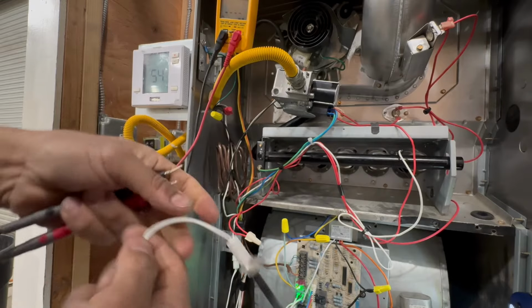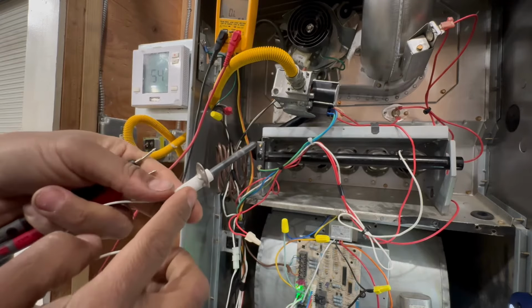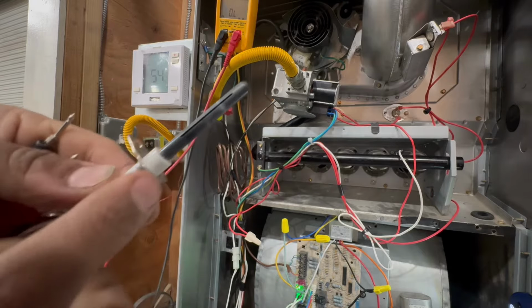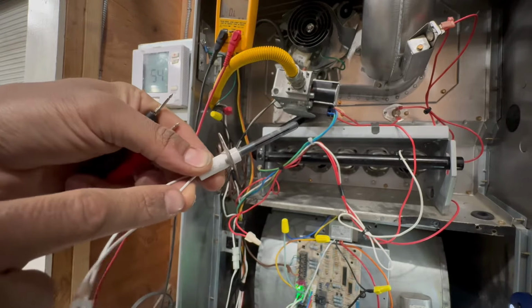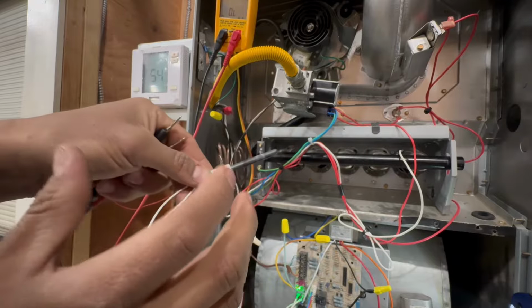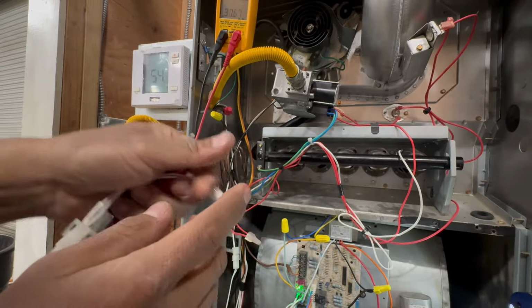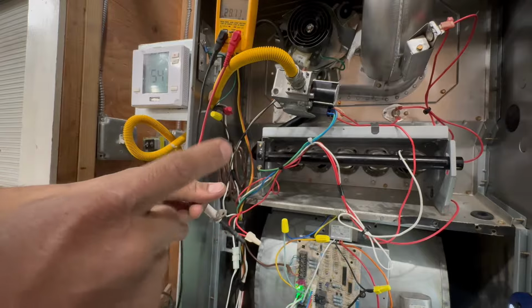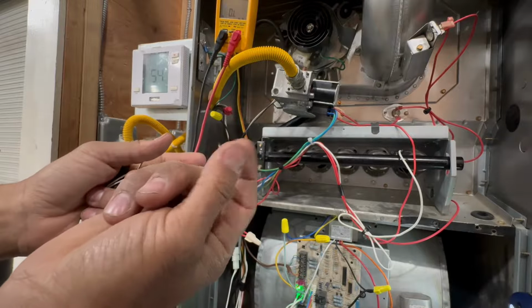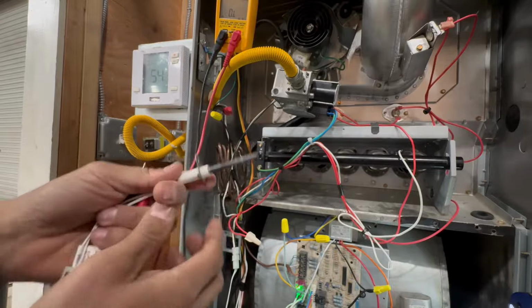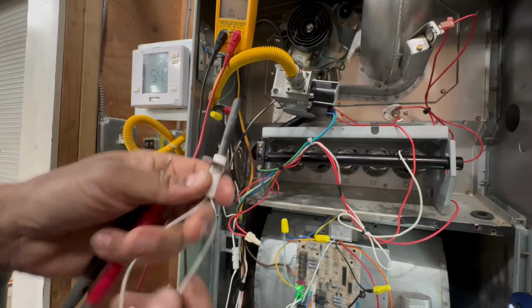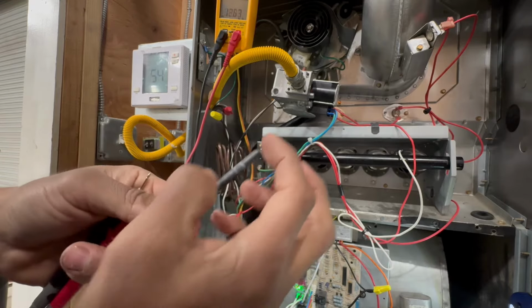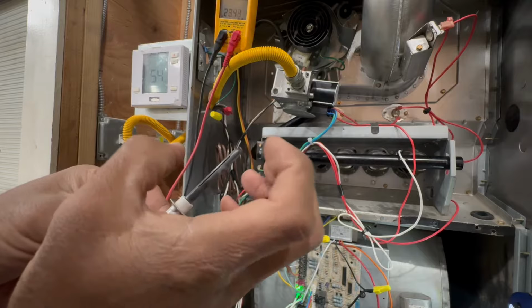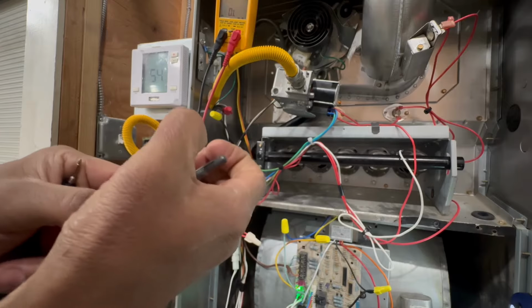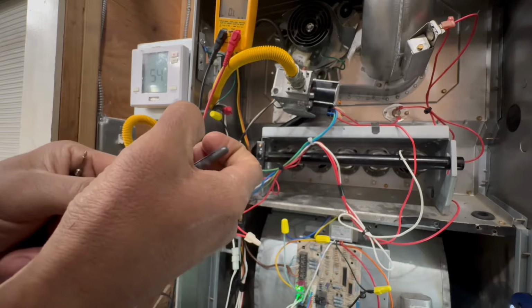The idea is that it's going on one wire, right? It goes on one wire, and you can kind of see it right there. There's a little gap in between, but the idea is that there's a path from here to here. Remember what I said about 120 volts, black and neutral, or even 24 volts, hot and common? They can't touch each other because they'll start to spark, right? They can't touch each other. So in this case, in a way, they are touching each other, but they have this special piece here, and it basically collects that current, that heat, and that's why it turns cherry red. So that's all it's doing with the hot surface igniter.